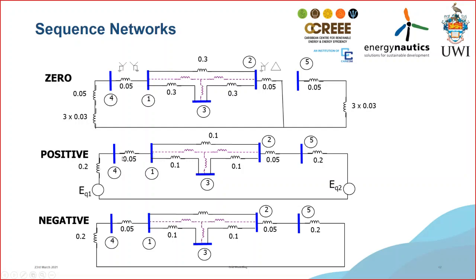Anyway, the impedances are all the same once there's no rotating equipment on the system. The only impedances that would change are the impedances of motors and, of course, the generators. If we look at the zero sequence, however, the zero sequence depends on whether there is a path through Earth for the zero sequence currents to flow.